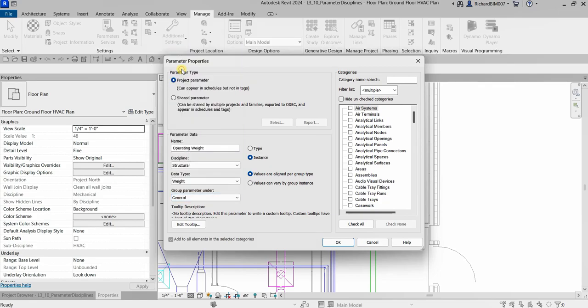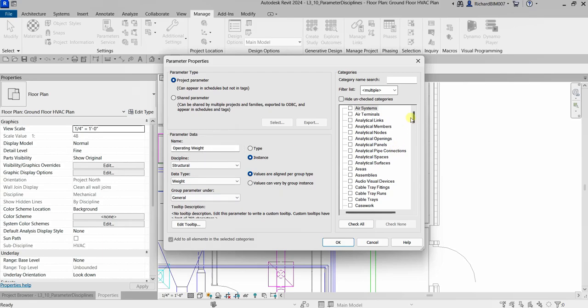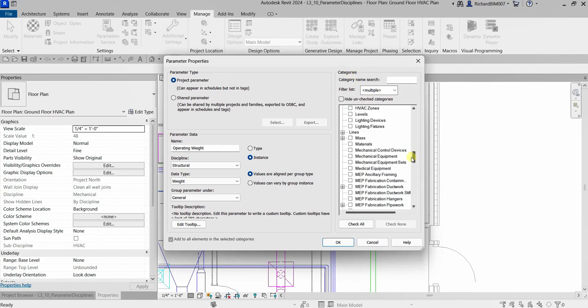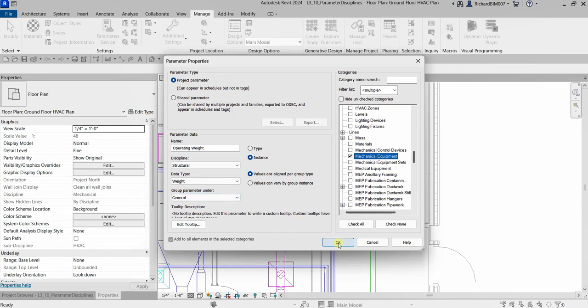For the discipline, I'll specify Structural. For the data type, I'll set it to Weight. For the Group Parameter Under, instead of Other, I'll specify General. Group parameters include things like Graphics group, Underlay group, etc. — I want Operating Weight under the General group. Then I'll specify the categories — I'll scroll down and look for Mechanical Equipment, so every time I select an instance of a mechanical equipment, I'll see the Operating Weight parameter in the properties under the General group.